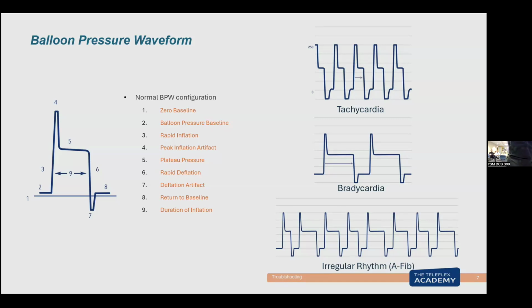So it plateaus out. At the end of the plateau, that's the end of diastole. Now the pump pulls the helium back to the bellows, goes past that transducer again, so we get the fling artifact, the opposite of this, down below zero and back to zero. That's how this is created. That's why we see one of these every time the balloon goes to inflate. So width always represents how long the balloon is inflated. When they're tachycardic, it's pretty narrow, but it always comes back to baseline before it inflates.